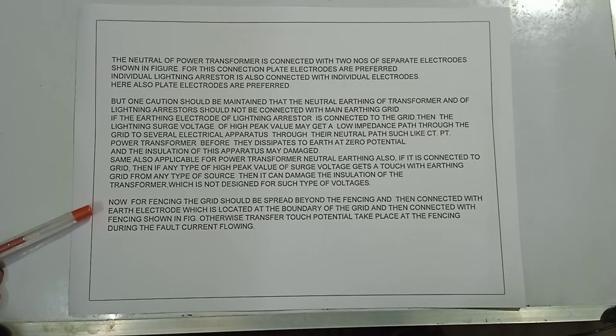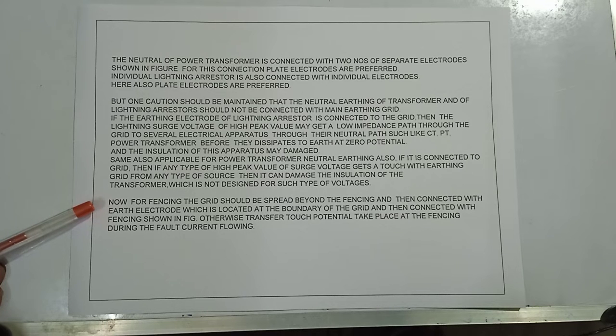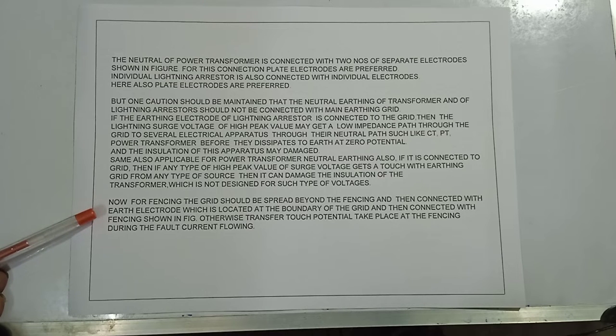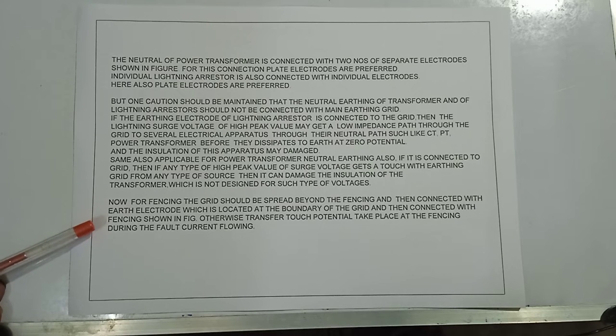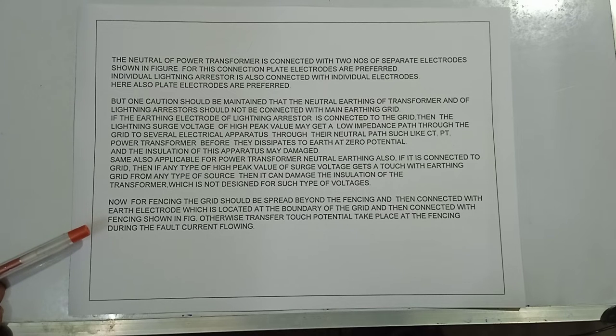For fencing, the grid should be spread beyond the fencing and then connected with the earth electrode located at the boundary of the grid, then connected with the fencing. Otherwise, transfer touch potential will occur at the fencing during fault current flowing.